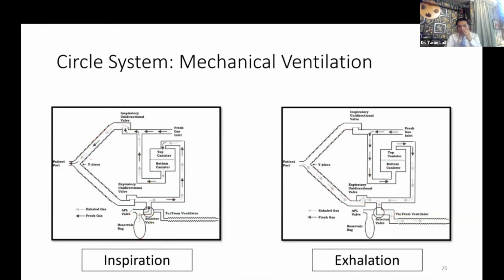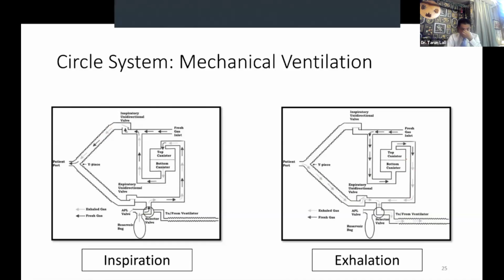circle system. Now, the question that many of you sometimes ask is why is the ventilator kept upstream of the CO2 canister? Can't the ventilator be somewhere here? Then the ventilator only has to push this much. Now the ventilator has to push through this much extra resistance. So yes, some machines do come with a ventilator which is placed after the CO2 canister.